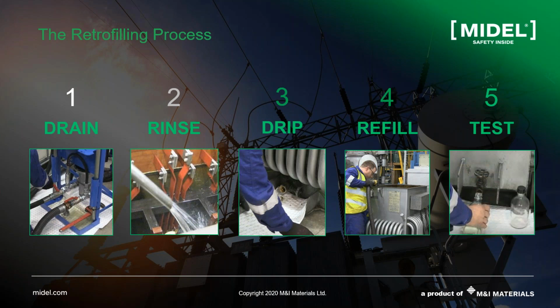To aid our draining efforts, we start rinsing the winding, which is the second step. Usually we recommend rinsing with 10% of the transformer volume with hot MIDEL or hot ester. Elevating the temperature of the ester will reduce its viscosity and allow it to go through the cooling ducts within the transformer, removing sludges and clearing mineral oil as much as we can. This is the rinse step. The third step is dripping. After we rinse, we allow the transformer to settle and drip for 2 hours. This will aid us in removing as much of the residual mineral oil as possible.